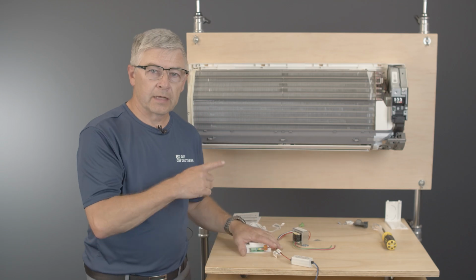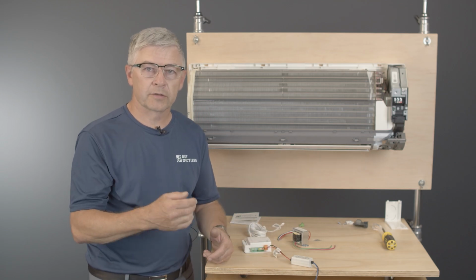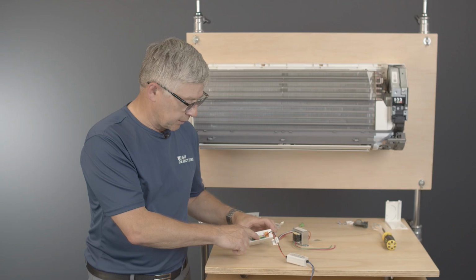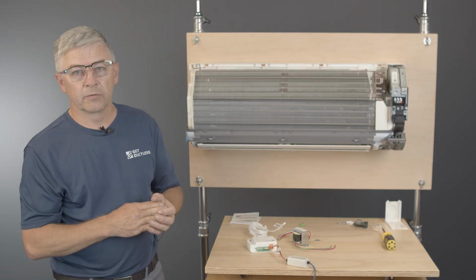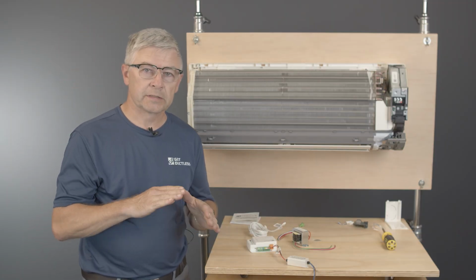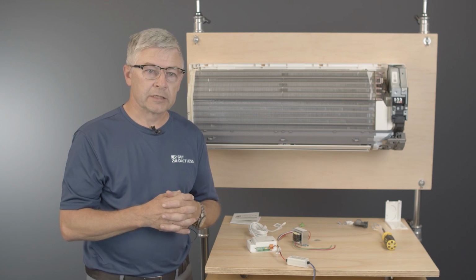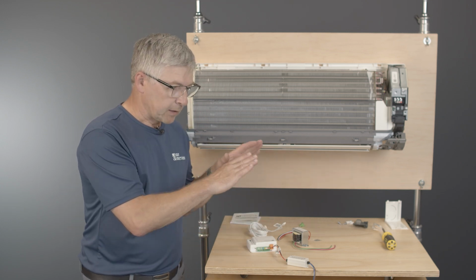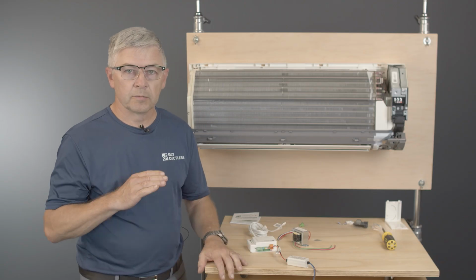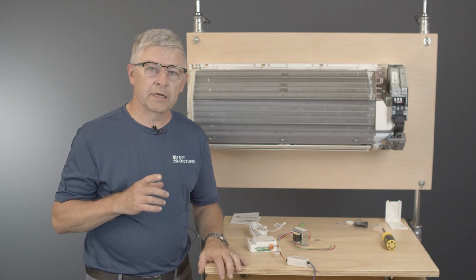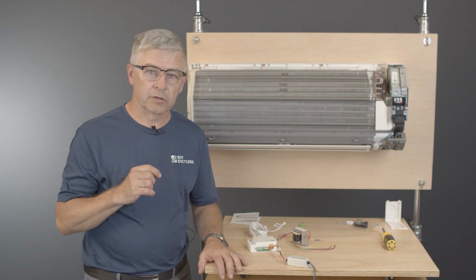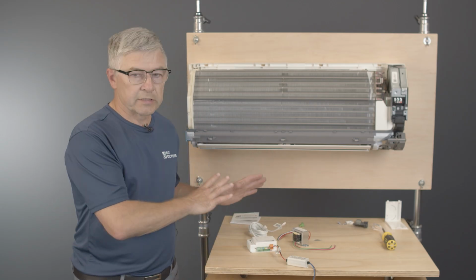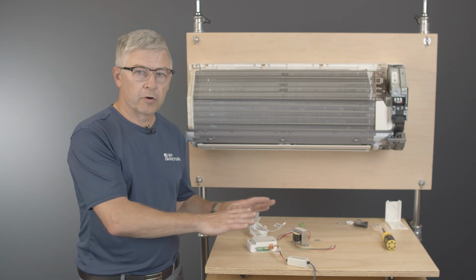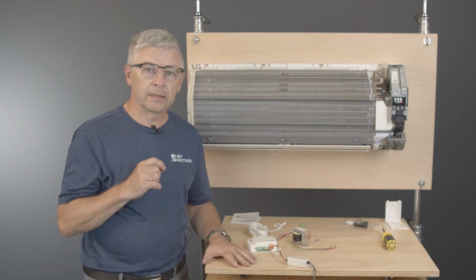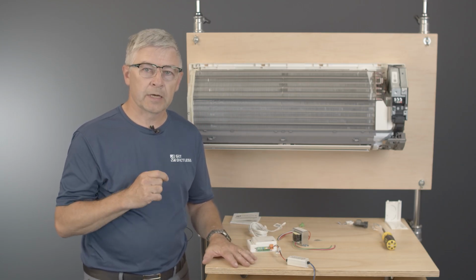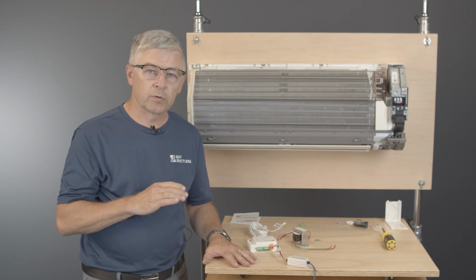And then you connect the other side of the thermostat wire to the actual thermostat itself according to these letters. Then you will need to follow the directions to set up your third-party thermostat. And specifically for this case, you need to keep in mind your third-party thermostat has to be set up as conventional, not as heat pump. Even though this is heat pump equipment, it's a little bit different protocol of communication. Again, your third-party thermostat has to be set up as conventional, whether one heat, one cool conventional or two heat, two cool conventional.